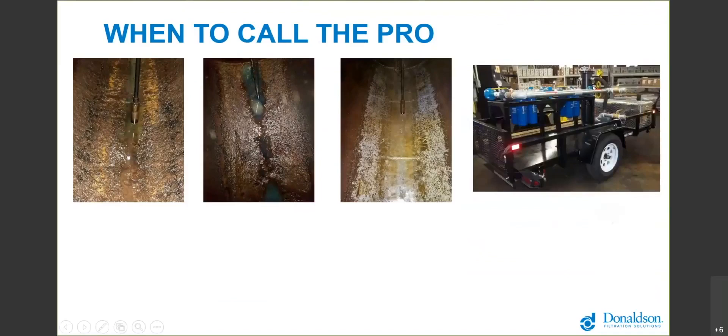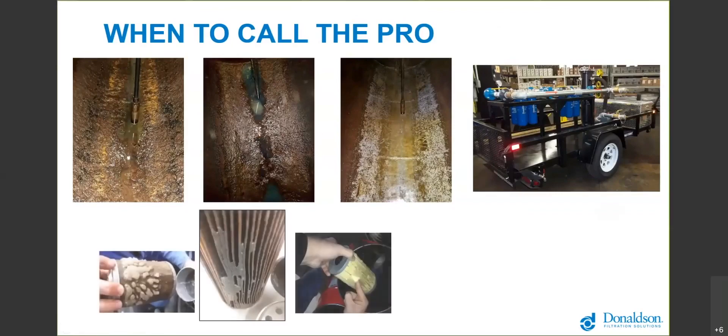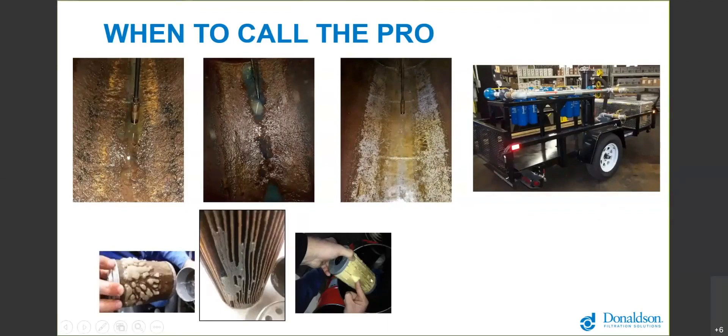Some of our distributors have applied pre-filtration. In this case it's a bag filter, which is pretty affordable filtration. This was a 10,000 gallon tank. You would run it down to where you only had about a thousand gallons of fuel left in it. You would try and save what you could save and the rest you would basically try and throw away. You might put this dirty contaminated fuel through this bag filter until you stop plugging bag filters, and then you would use the blue carts and return it back to the tank knowing that it was clean and dry once your tank was clean.